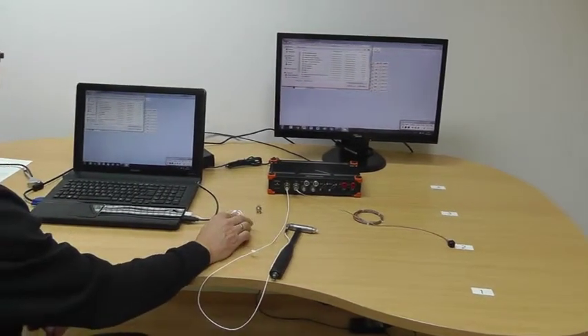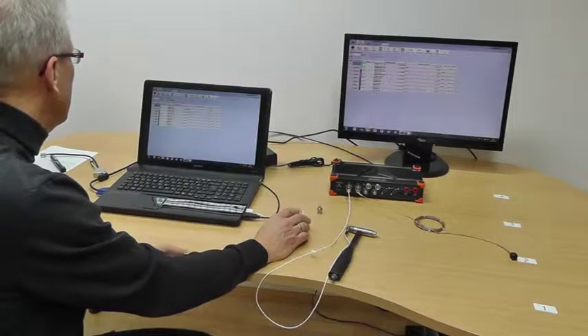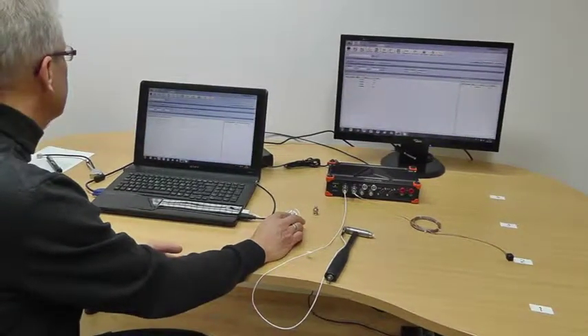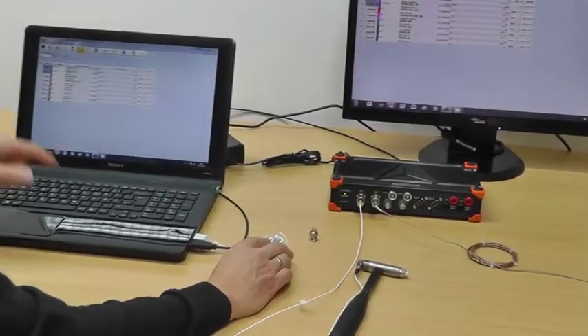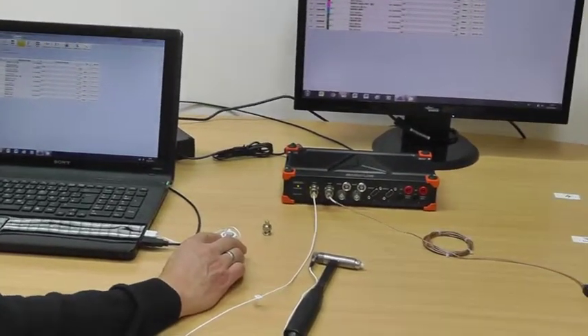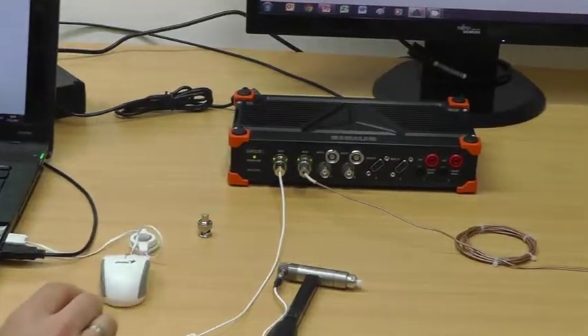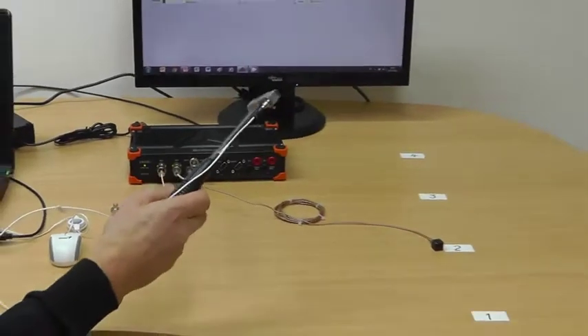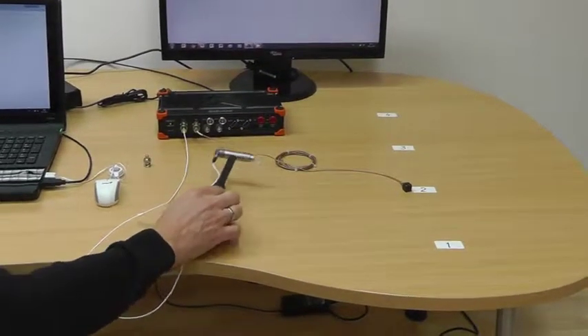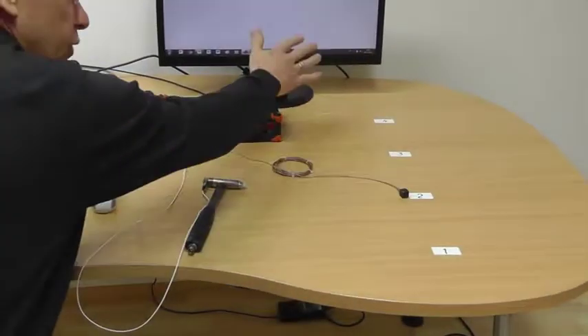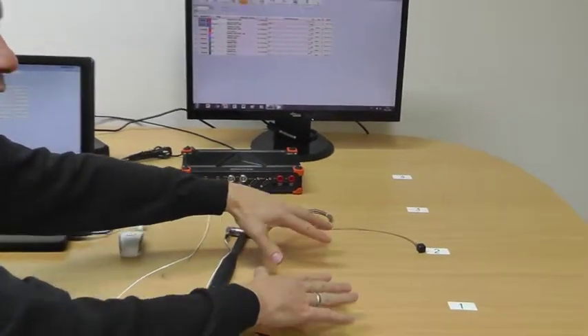Very simple demo. I have prepared one setup, and this setup already shows two channels in the input. Let's look at the analog input channels: there is one excitation channel and one response channel. The excitation is my hammer, and the response is this sensor located on position number two. I want to see the structure of this table — how it moves, where the natural frequencies of this body are.